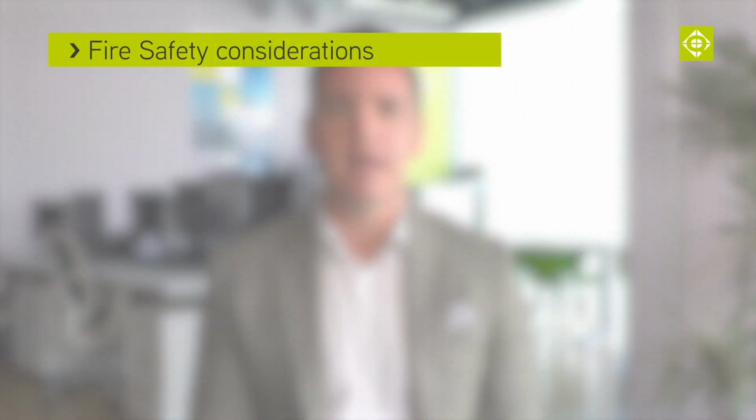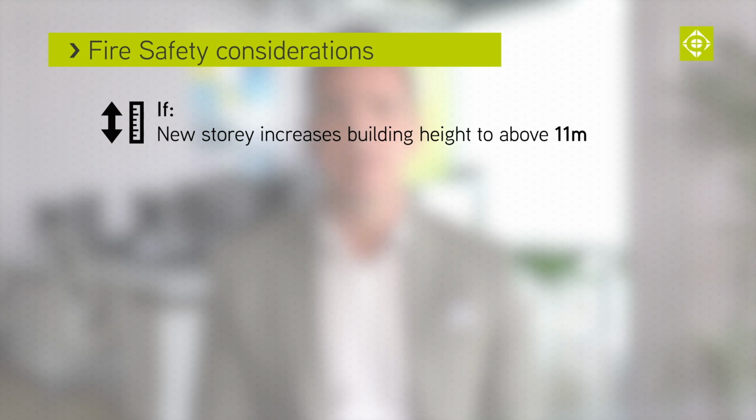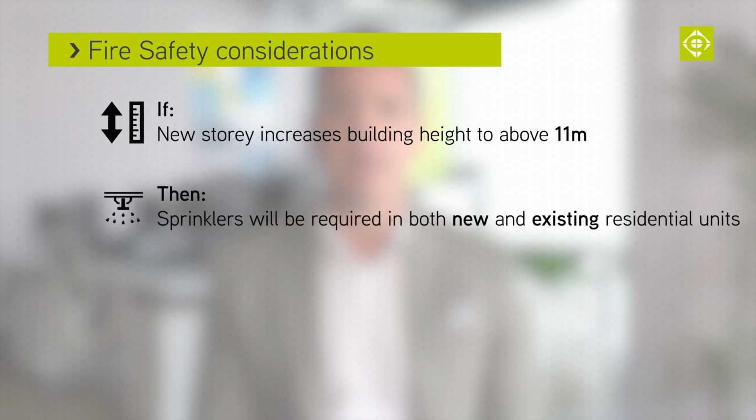Secondly, under changes to Part B from November 2020, if a new storey increases the height of a building to above 11 metres, sprinklers will be required in all new and existing residential units in the building.